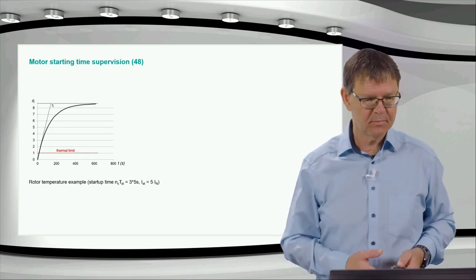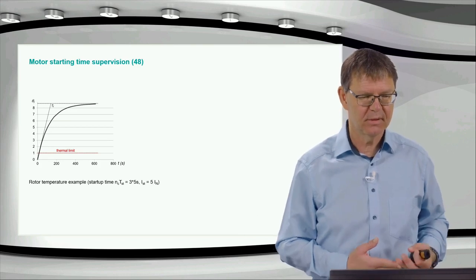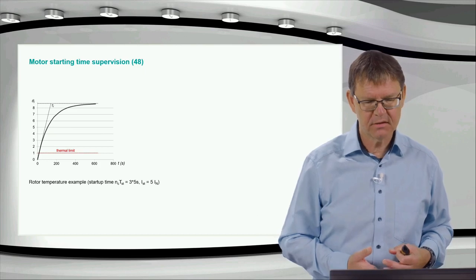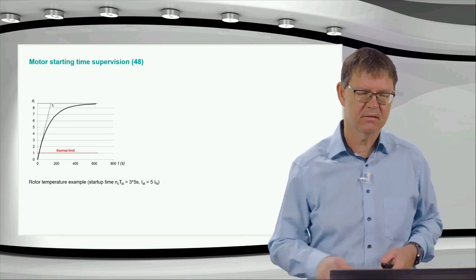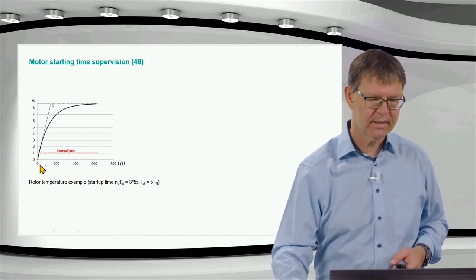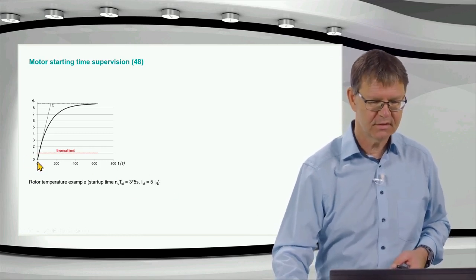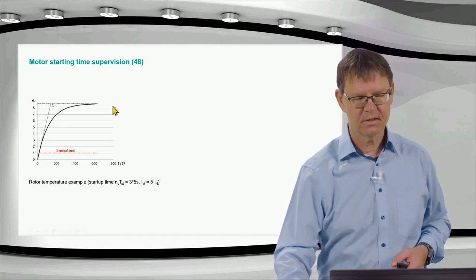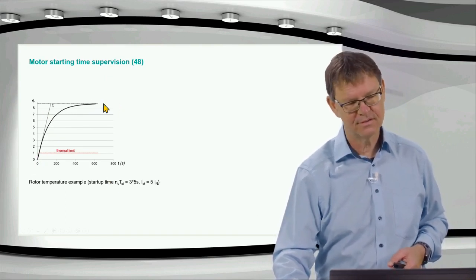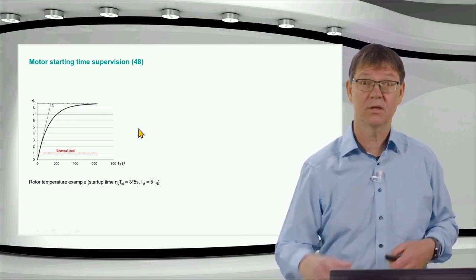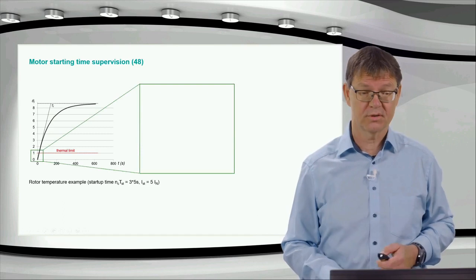Here I have again this rotor temperature example. Startup time 5 seconds, 3 times 5 seconds, and the starting current 5 times nominal current. After 15 seconds, I'm here. And if the situation prolongs, you would come to temperatures like that. You see much too high temperatures.